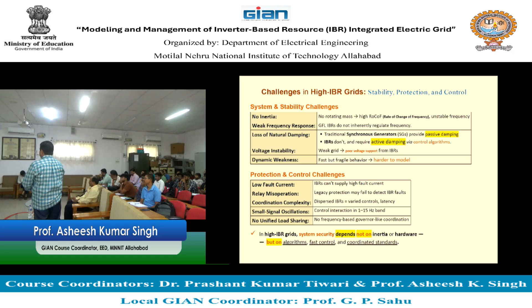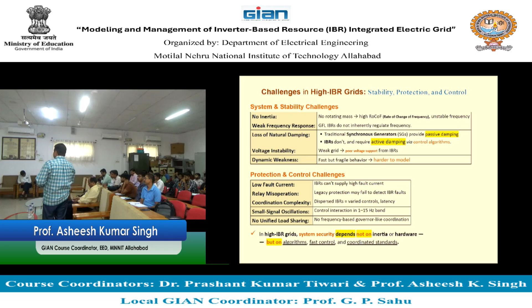Clear? So varied controls, latency, bandwidth requirement for control, because it is very difficult to have a centralized control for them, right? So you have to put this control at local levels. Small signal oscillations, the control interaction is in the band of 1 to 15 Hertz. No unified load sharing, means no frequency based governor-like coordination. So this is a challenge to handle.